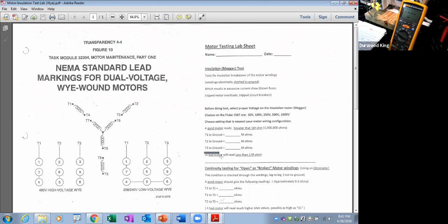So your reference point is going to be this. A bad motor will read less than 1 megohm, or one mega is going to be 1 million. So if you're less than 1 million ohms on insulation resistance, it's going to be considered a bad motor. If you're over 1 meg, then that's their borderline. They say if you're over a meg, you can let the motor run, even though it is developing leakage. They say in general, that's a general figure right there. It's kind of sort of pretty much accepted.